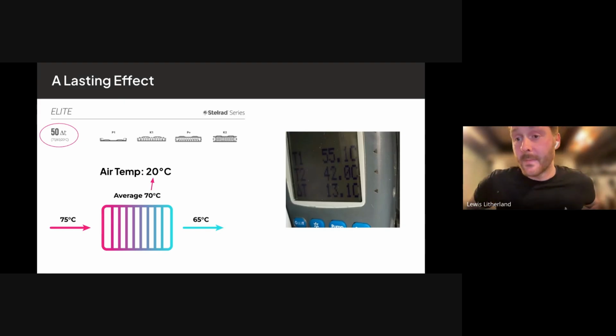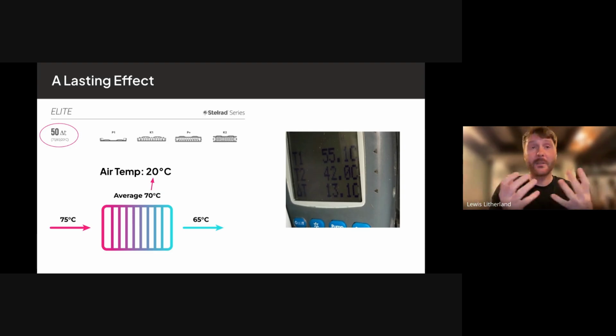This is me basically saying that I got it wrong. This is in my mum's property when I fitted the boiler there, maybe coming up to 10 years ago now. I didn't understand any of this. I still fitted it as if it was a non-condensing appliance. I'd never been taught any different.